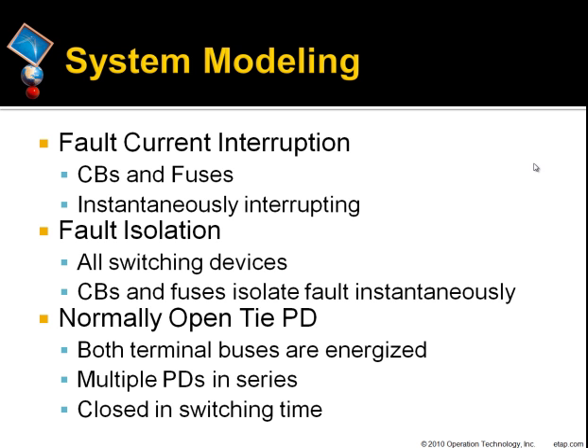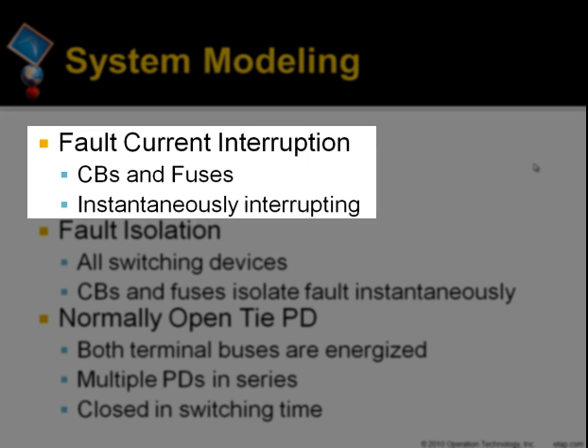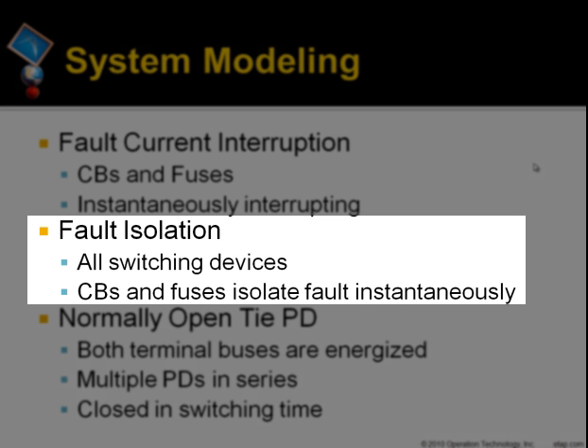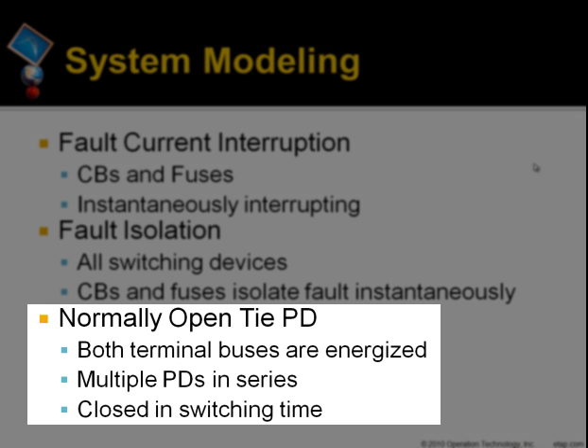For system modeling, ETAP considers the following. For fault current interruption, only overcurrent protection devices such as circuit breakers and fuses can interrupt fault current, and interruption is assumed to be instantaneous. For fault isolation, all switching devices can isolate a fault, but circuit breakers and fuses isolate a fault instantaneously. For normally open-type protective devices, the two terminal buses are energized. Several protective devices can be connected in series with more than one open, and an open-type protective device can be closed in switching time to provide backup power.